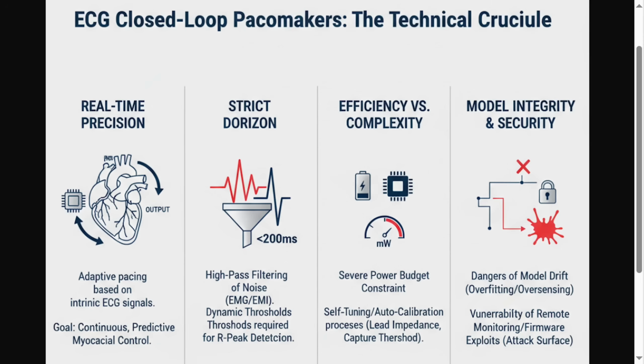Oversensing, my favorite technical flaw. That's when the device misclassifies non-cardiac electrical activity, like chewing gum, muscle tremor, or electromagnetic interference from the hospital MRI scanner, as a legitimate beat. Essentially, the pacemaker has performance anxiety and keeps firing pulses when the heart is already working fine. Precisely. And the computational challenge is filtering out that non-cardiac noise without simultaneously smoothing out or delaying a truly critical arrhythmia signal. We use adaptive thresholds that fluctuate based on the preceding R-wave amplitude, trying to dynamically optimize the signal-to-noise ratio. But those thresholds introduce their own calibration problems.